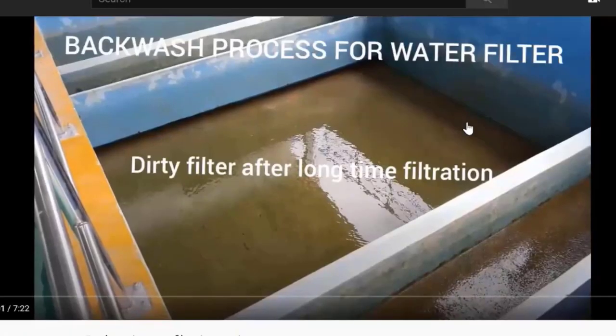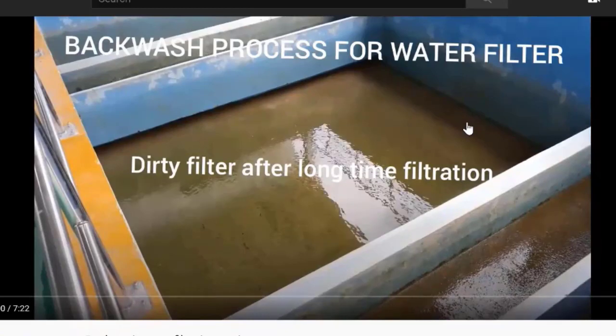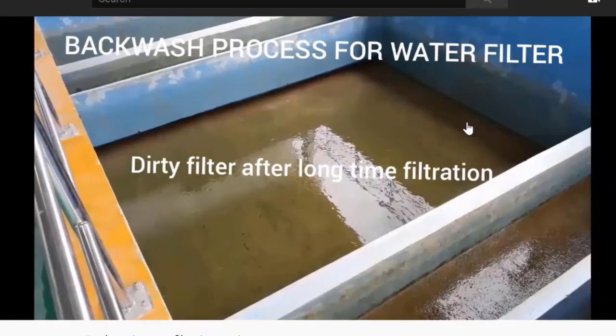So what's happening right now is the video starts with backwashing. The filter has been operational, but either the head loss limit or the turbidity limit was exceeded, and at that point this triggers backwashing, and the backwashing process actually starts.